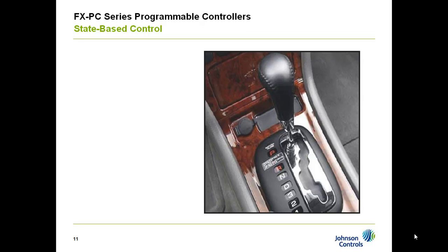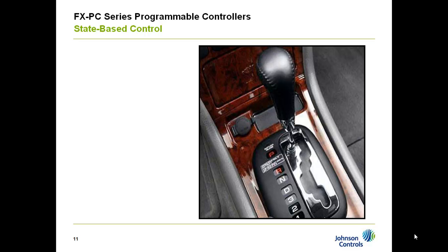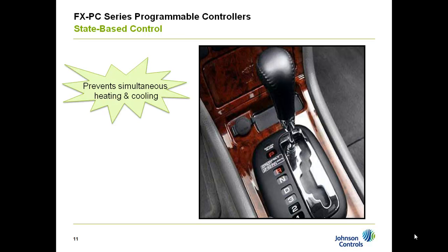The standard system applications are designed using state-based control, which provides truly advanced control capabilities. State-based control is similar to a car's automatic transmission system, where it mechanically prevents you from being in both drive and reverse at the same time. Similarly, state-based control prevents FX-PC controllers' control logic from being in cooling and heating at the same time, which is an energy waster.